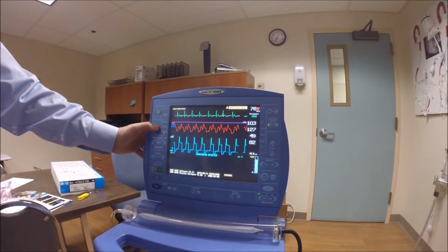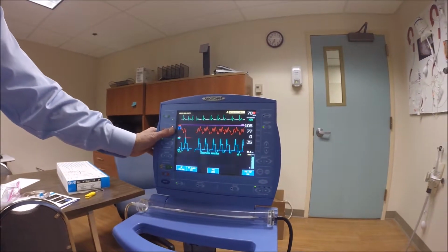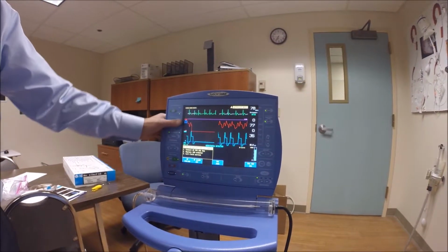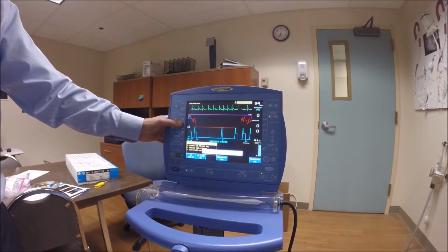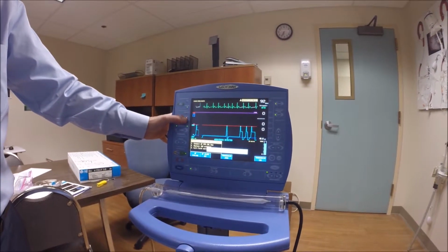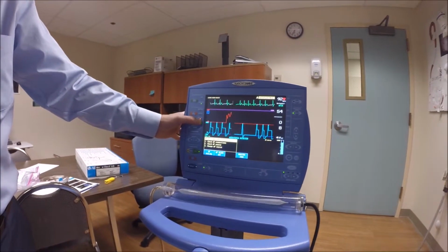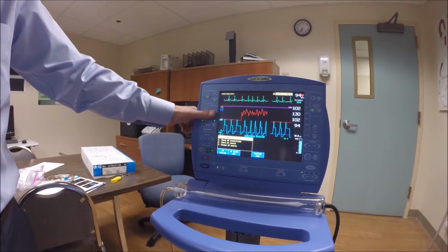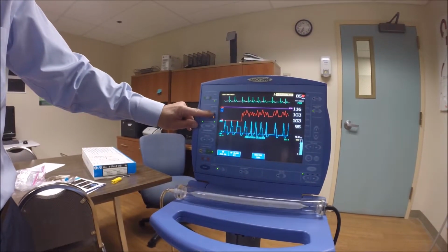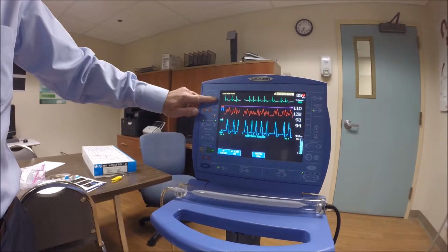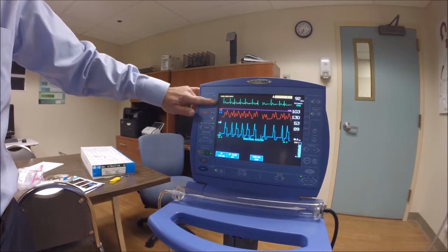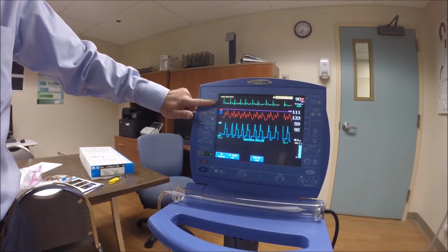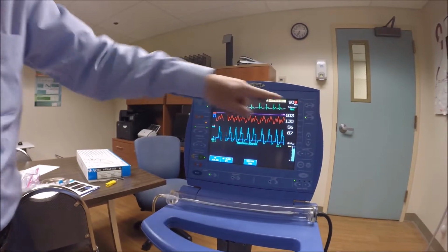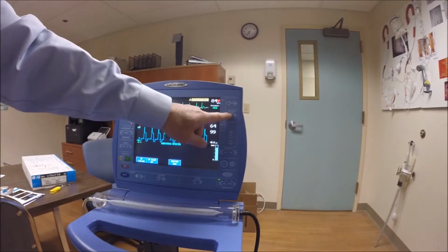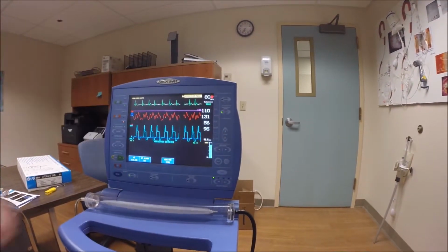Your AP select button will always say fiber optic if you're utilizing a fiber optic catheter. If you're not using fiber optic, then it'll be on the transducer. Mine is on monitor because I'm using a simulator. But again, you'll be on fiber optic or transducer. Your ECG will also say skin and not monitor. Again, I'm using a simulator, but yours will say skin lead. Again, here are your triggers right over here, your arrhythmia timing. This is your cursor button.